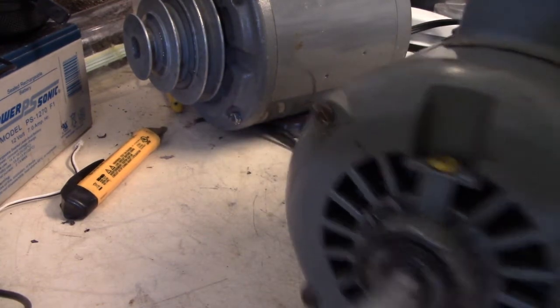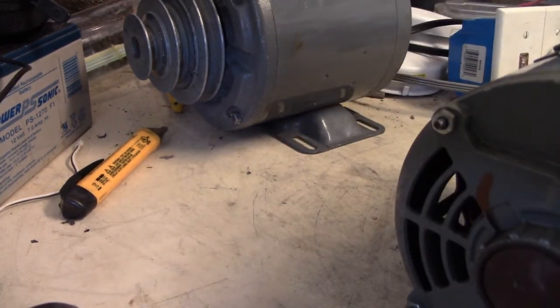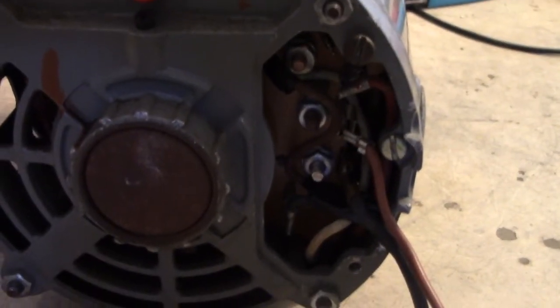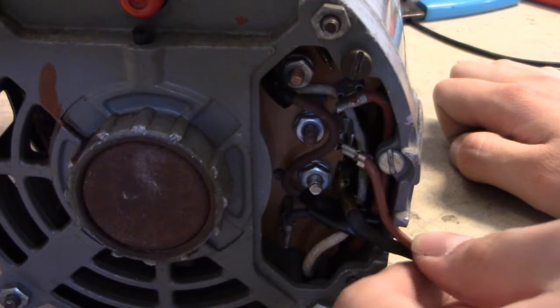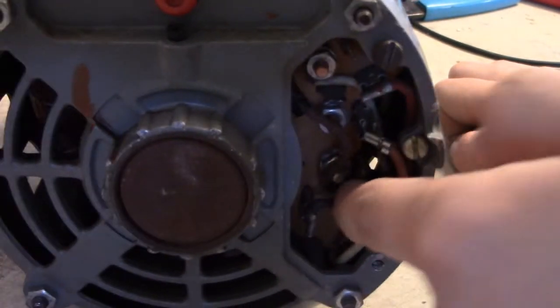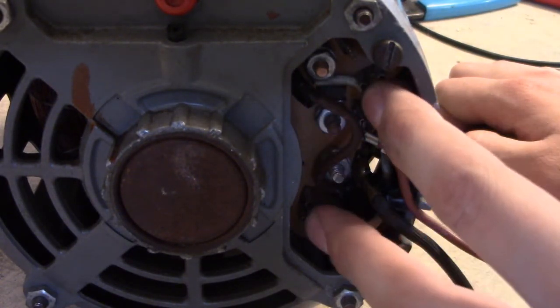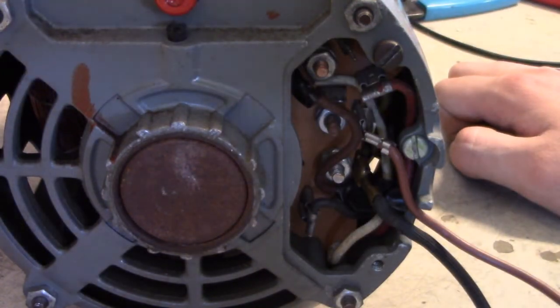Now if you have a motor like this right here, it looks a little different. This is a Dayton motor. Don't worry too much about the RPM on it. But as you can see here, the connections are a little different than what I showed you. Now basically, how you swap the rotation on this one, you see this black wire right here, down in here, like this black wire with this lead connector, and this red wire, you simply just swap both two of those wires the other way, and it goes the other direction, which is pretty cool.